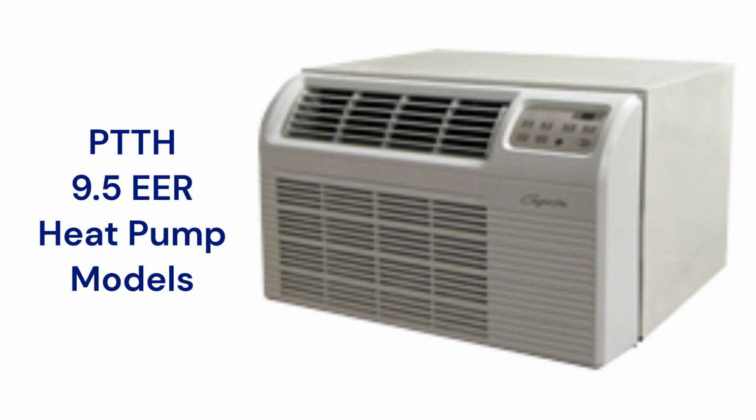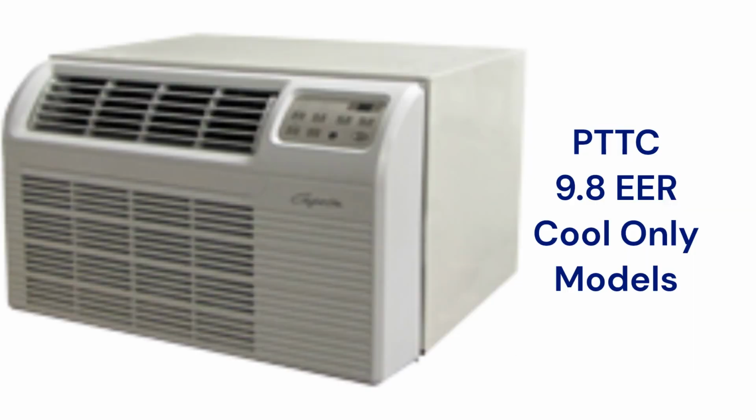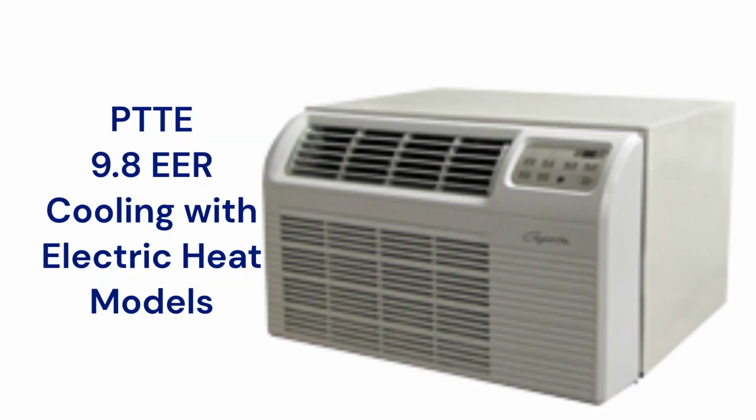if the compressor fails. The PTTC models are cooling units with a 9.8 EER efficiency rating, while the PTTE models have electric strip heating. The units use basic rotary compressors and have a noise rating that is roughly equivalent to that of normal adult conversation.